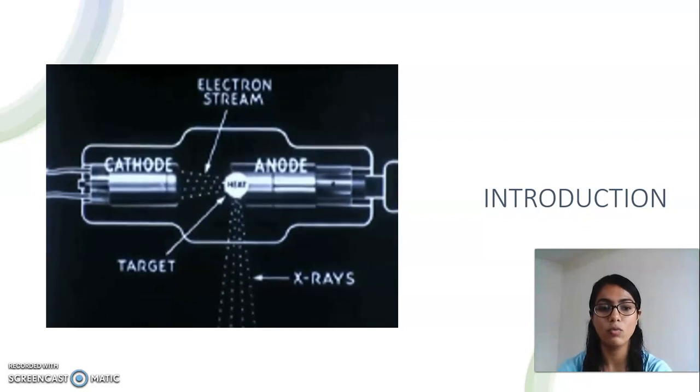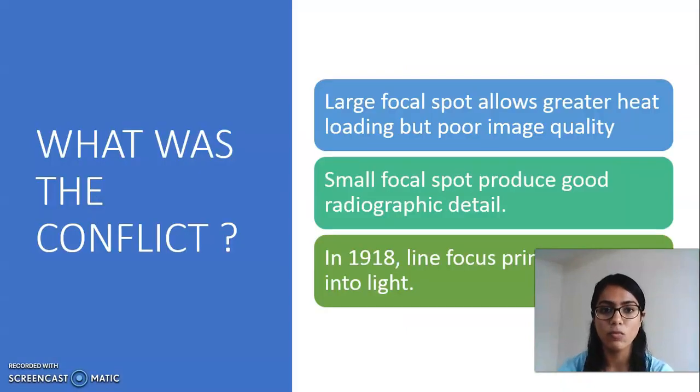Here comes the conflict. What was the conflict? The conflict was larger the focal spot allows greater heat loading but poor image quality. Small focus spot produced good radiographic detail but heat dissipation was not effective, it caused further damage to the target.